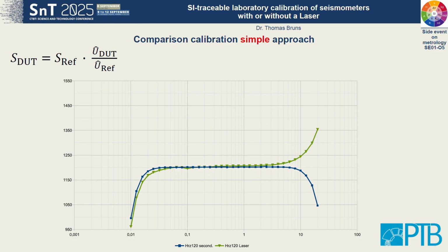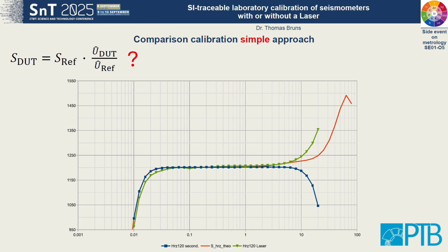It's wrong because we did that measurement on that shake table I showed before, and we used the laser in combination with this comparison setup. So we know the primary results for the same measurement, and the primary results for this measurement look like the green curve. Well, they should look the same if they are valid calibrations. They don't, so something is wrong here. And if you add the manufacturer's information, you get this red curve. We call this the theoretical curve because it's the equation from the manual that is applied here. And that looks also quite different from both of them. Here you see problems also in primary calibration, apparently.